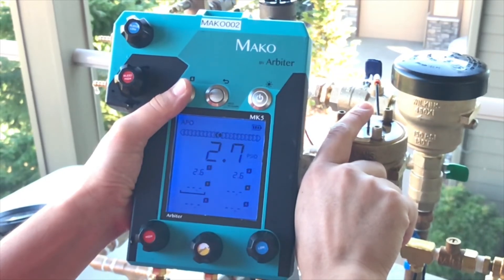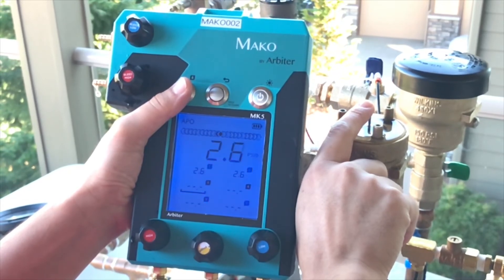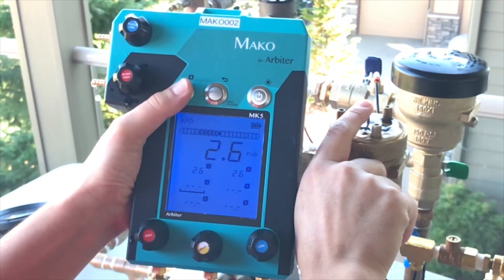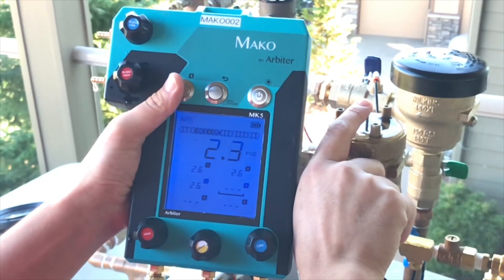In the saved values you can see that we've captured 2.6 psi before. You will see the valve open on the right side with the rippling water. When the user feels that valve open, or when they see the rate of change graph move fully to the left, they can press the capture button without looking.